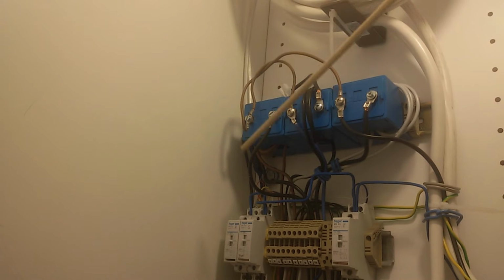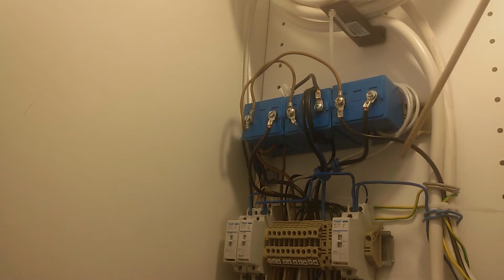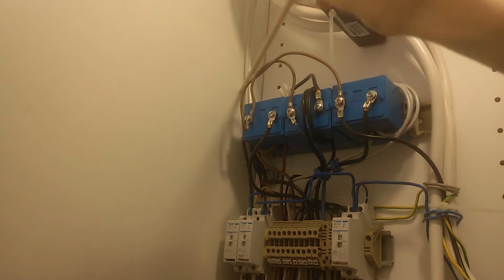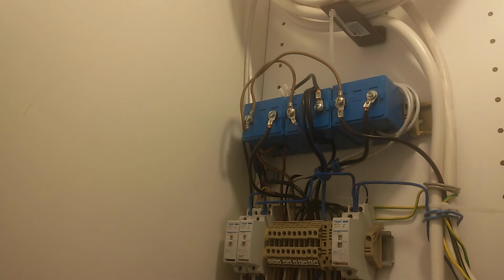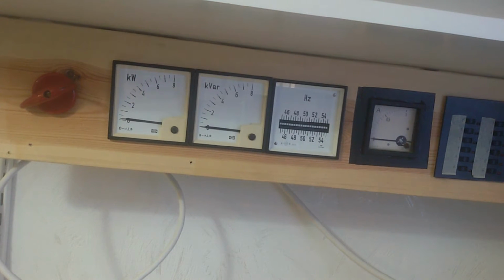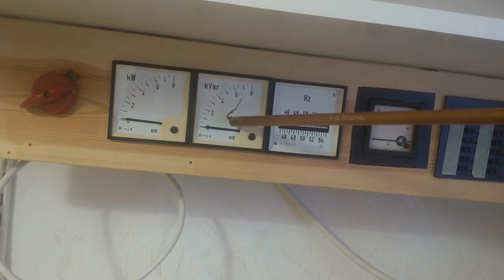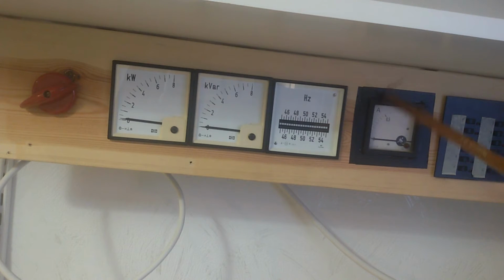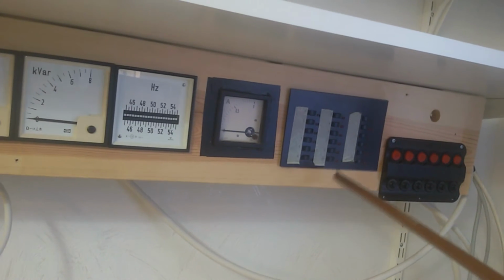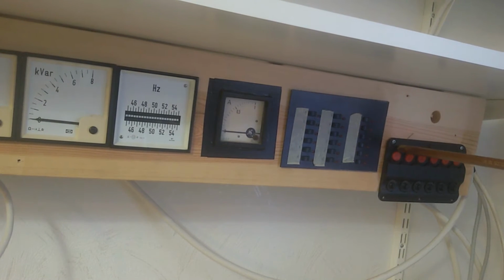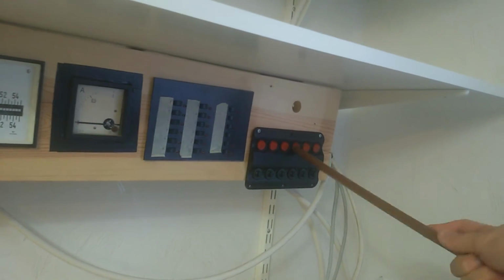Of course it's metal, so it needs to be earthed. And up here, common neutral on top. Here's a wire neutral that goes to the panel. So it's very important to keep that intact. And there are phase wires to phase monitoring from the relays. And here are the power meters. We got a kilowatt meter here, kilovolt amp reactive, hertz, and an amp meter for the UPS voltage coming from the inverters. A little board that is not connected anywhere. And here are some switches to relays. It actually operates those sockets on top. And this one is for a light. Yeah, so it's light and everything. That's good. Disconnect it. Yes, relays and stuff.